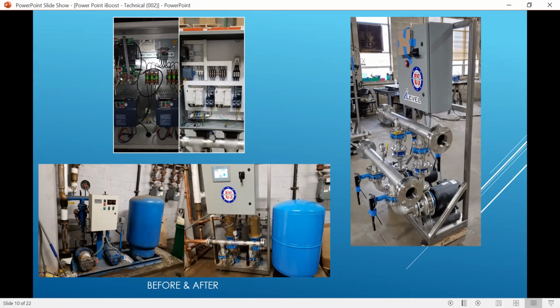That's our feel. We can basically build a system without it. It doesn't really matter. We have soft start mechanisms in our panels if we need it, so you're not running that pressure right up to the top of the building and it's slamming at the top of the pipe and then coming back down and causing a bunch of vibration in the building. But our feeling is that if you've got room for a tank, put it in.